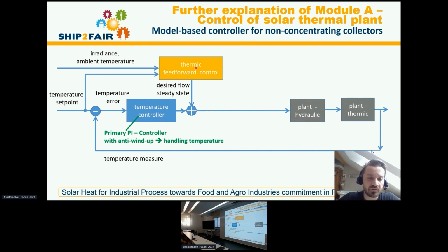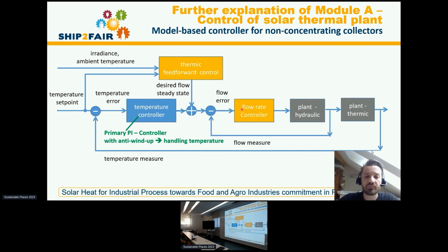This feed-forward control considers the solar irradiance, the ambient temperature, and the set point, and already calculates the desired flow for steady-state conditions, which is then added to the output of the PI controller. This gives us the desired flow we want in the solar collector, and then we have a secondary PI controller, also updated with an anti-wind-up procedure, for handling the flow rate. So it's a cascaded structure.